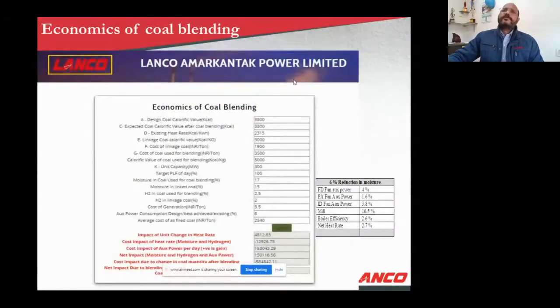So if we see the economics of coal blending, what are the elements? Like design coal calorific value, what we have, the expected calorific value, what we are targeting, existing heat rate, what is going on. These are the input parameters into the model. Then cost of the linkage coal, the cost of coal used for the blending, which we have options. So one can enter those values and see different results. If you have 2-3 types of coals available for blending, what is their cost? Then also what are the ingredients of those coals? Then unit capacity, then moisture in the coal used in the blending, moisture in the link coal. All these values we have to put into it.